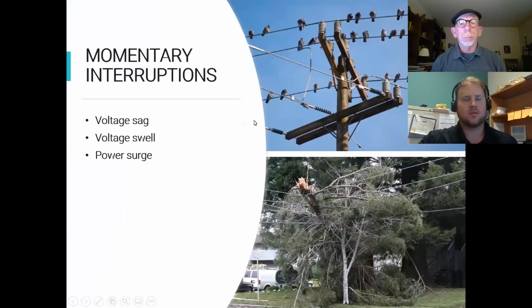Next, we have the momentary interruptions. These may include voltage sag, voltage swell, and power surge. Momentary interruptions are typically very fast events, in the microsecond to millisecond range, only going to last for a few power cycles of that 60 hertz power that you're getting. They are typically caused by an automatic switch or automatic circuit breaker closing, or recloser operation.